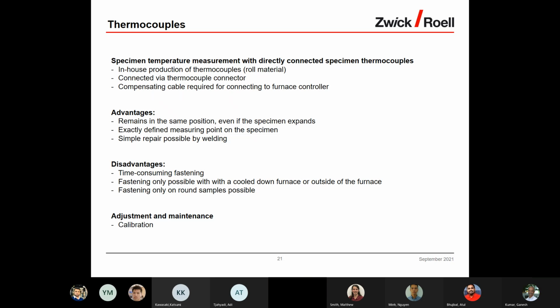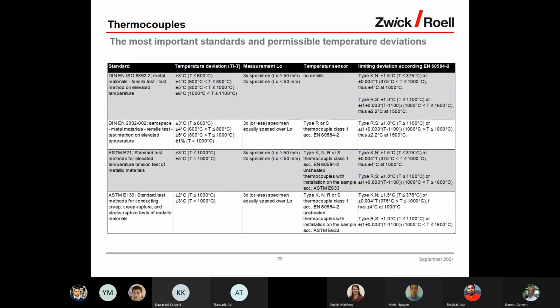Adjustment and maintenance, the calibration of the thermocouple. Here you can see the standard norms, the temperature ranges, the measurements L0, the type of the thermocouples. The most important standard and permissible temperature deviations are here on this page.